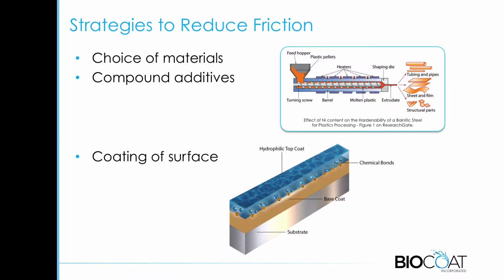Talk about the strategies for reducing friction. If you start from the beginning, you can go from the choice of materials of making your device. A low durometer PEBAX material is rather tacky and soft compared to, say, a PTFE material, which is very, very slippery, but it does not have some of the good bulk properties that you may want. You can choose within that some that have both inherent bulk properties and surface properties that would work out. A lot of times, though, you're wanting bulk properties that impart greater strength and stiffness, that would not translate to a lubricious surface.